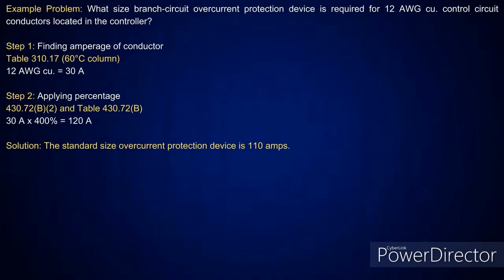All right. And the next one we're going to look at is control circuit conductors. Now, this particular one is where the conductors are located in the controller. And remember what I said when we were doing this. This is a verification for when you go look at 430.72B2. And I said when you're in there, below the table you're going to have your notes there, where all this ties in together. And basically, when I look at this, since you're inside the enclosure, I said you're going to be looking at table 310.17 because that's considered to be in free airspace.